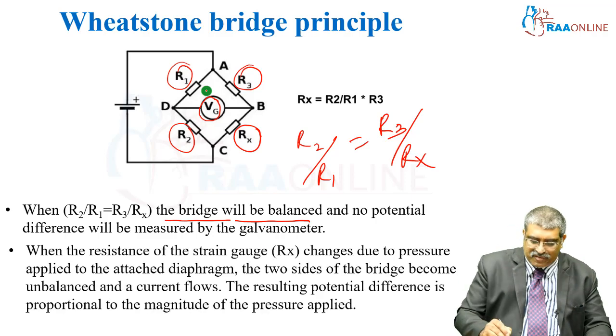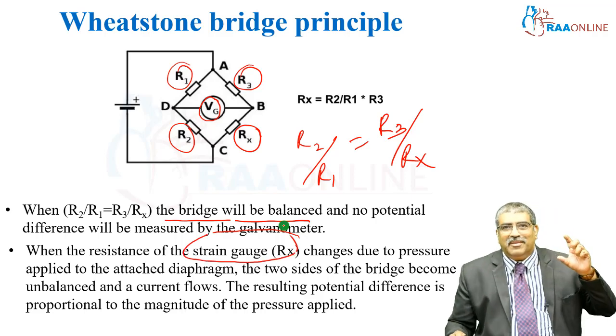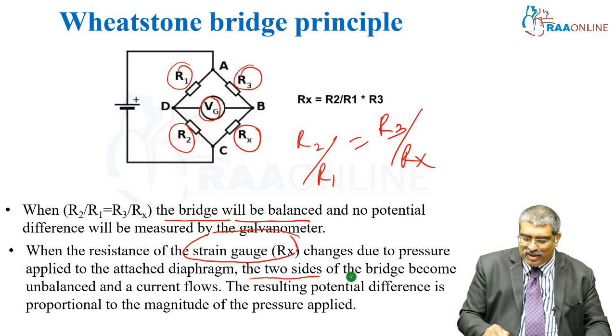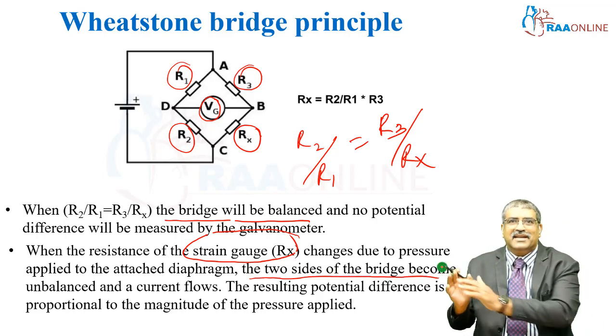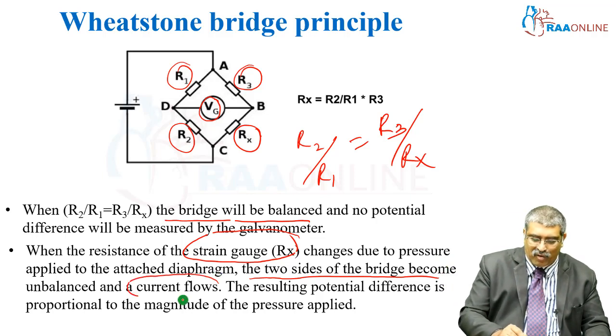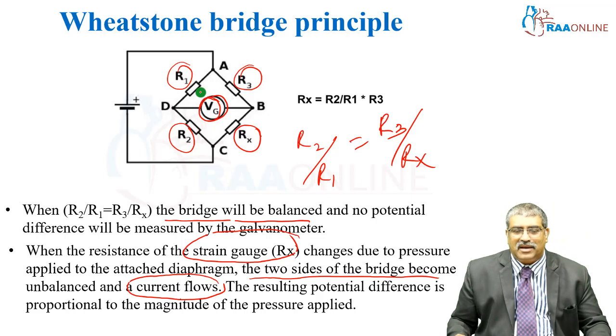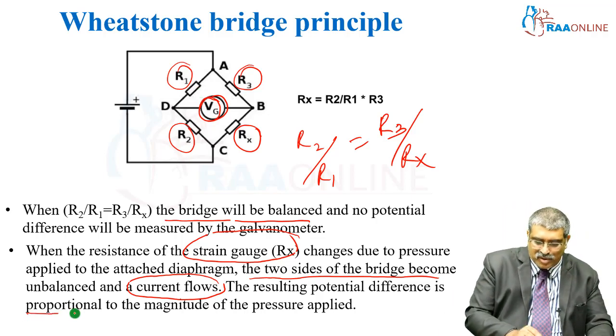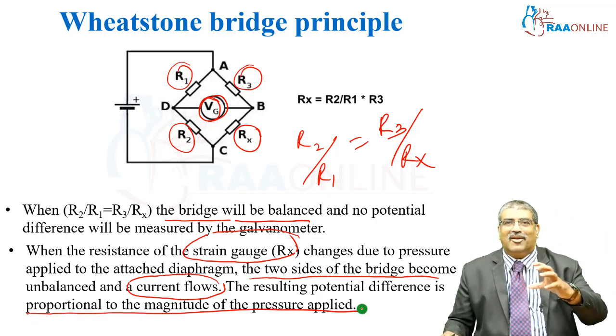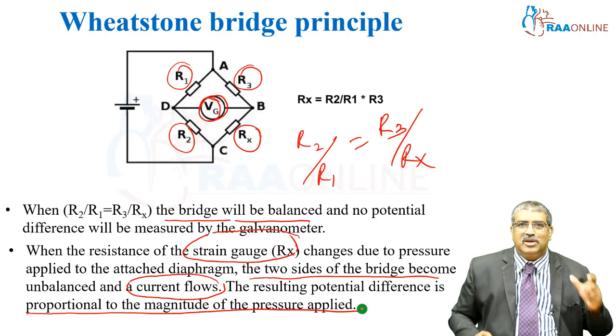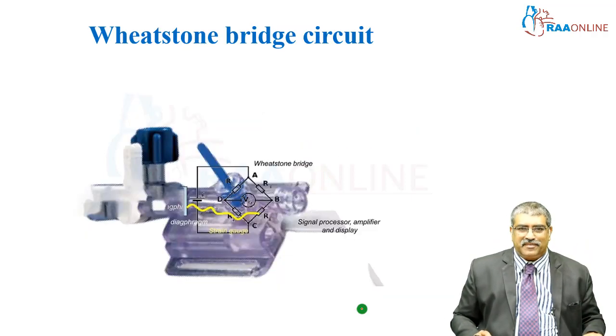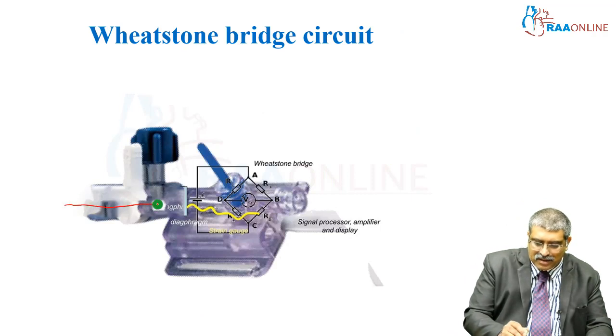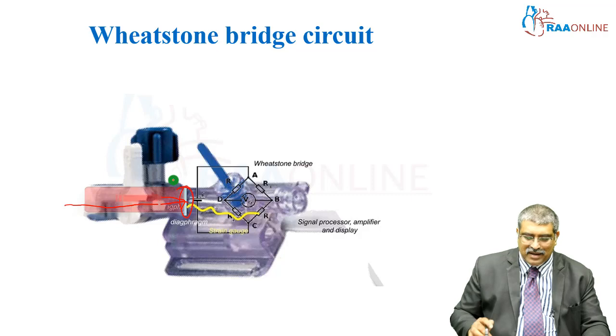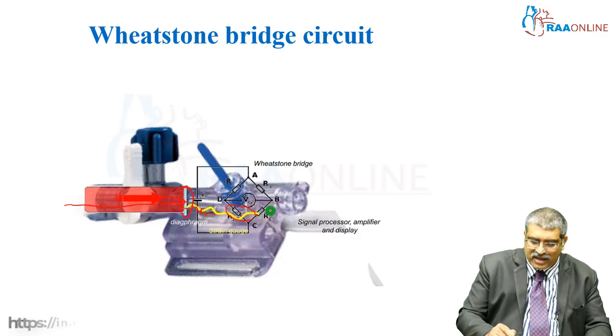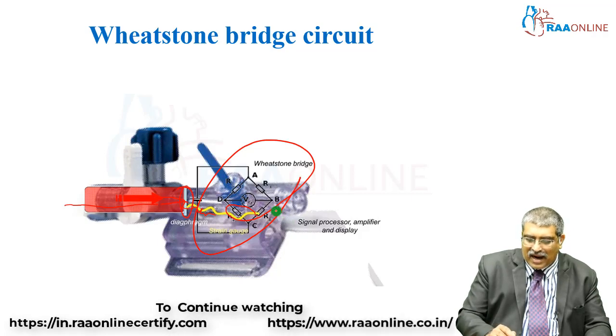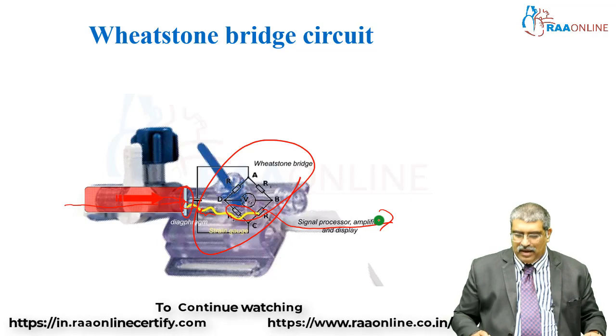Now, when the resistance of the strain gauge is altered due to the pressure applied to the diaphragm, the two sides of the bridge, R1, R2 and R3, Rx, are unbalanced and a current flow happens which is recorded by the galvanometer, and the resulting potential difference is proportional to the magnitude of the pressure applied on the diaphragm. This is how an arterial line works, based on the strain gauge and Wheatstone bridge. Here you can see the pressure being transmitted to the diaphragm, which is located here. As the diaphragm is altered, your strain gauge and Wheatstone bridge come into picture, and this is signal processed, amplified and finally displayed.